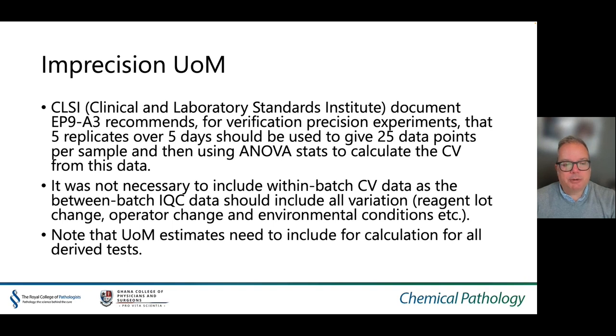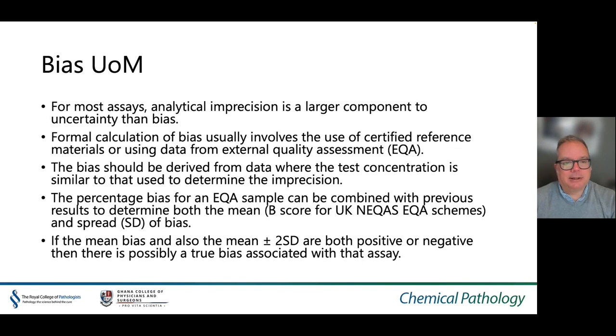Uncertainty measurement estimates need to be included for the calculation of all derived tests. For most assays, analytical imprecision is the larger component of uncertainty compared to bias. Formal calculation of bias usually involves the use of certified reference materials or data from external quality assessment schemes. The bias should be derived from data where the test concentration is similar to those used to determine imprecision. The percentage bias for an EQA sample can be combined with previous results to determine both the mean (the bias score for UK EQA schemes) and the spread or standard deviation of bias. If the mean bias and the mean plus or minus two standard deviations are both positive or negative, there is a possibility that a true bias is associated with that assay.